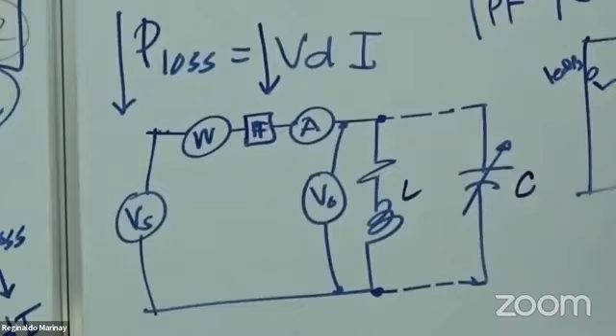It becomes a resonance condition. Now it also has a tendency to become leading - the system can have a leading power factor. What will be the effect? If the system becomes leading, for leading power factor, your load voltage becomes greater compared to your source voltage.